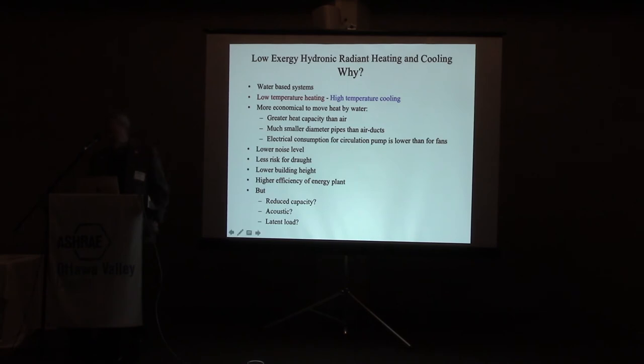And finally, acoustics. That has been one of the discussions, because if you have a bare slab or metal radiant panels, you don't have the same absorption that you normally have for a suspended ceiling. So in some of the first buildings I was involved in, they found other ways of absorbing some of the sound. You could put in a carpet, but I would not recommend carpet, but you can make furniture also wooden surfaces. We have a higher surface area if you put small holes in them, so they absorb more of it.